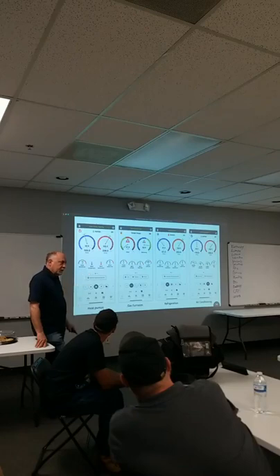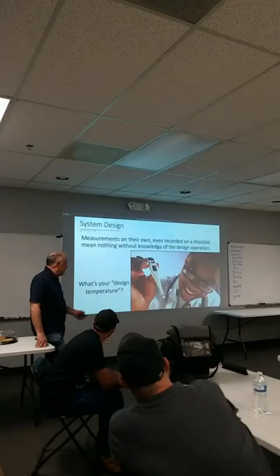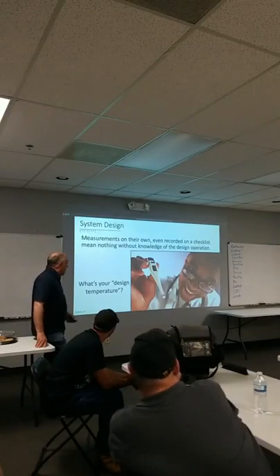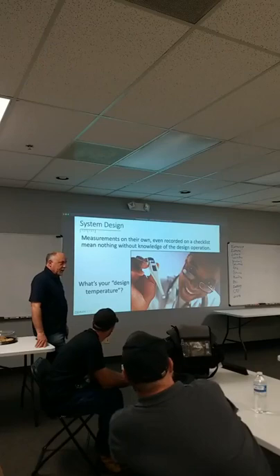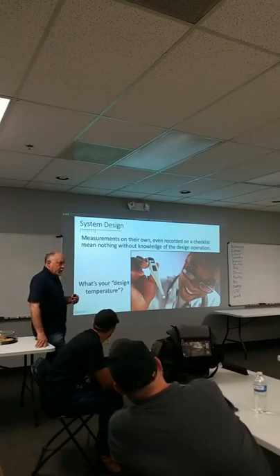It's not a limitation of the software, it's a limitation of the equipment. The equipment's just not designed to be charged in the heating mode, right? One of the things I always want to reinforce here is that before you make any single measurement, before you hook up a gauge, before you hook up a thermometer, before you do anything, you need to know what the measurement should be, right?